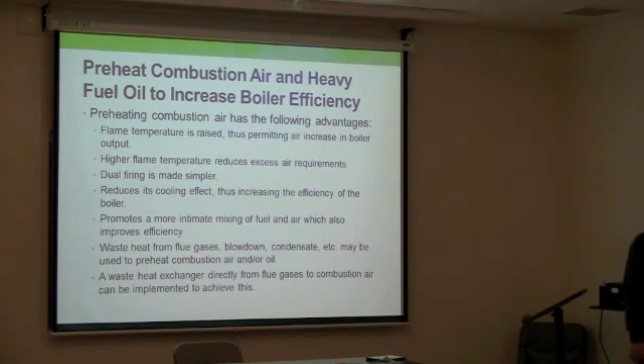A lot of times the combustion gas, the flue gas that is leaving the stack and is supposed to go to the air, right? You can use it for different purposes. It's very hot air. Why do you want to let it go? Of course that hot air is full of CO2 and NOx. You cannot use it as air conditioning, for example, and put it inside the room, right? But you can use it in an air-to-air heat exchanger, heat up clean air, and send it in the room. You can use that hot air to preheat the water that is coming to the boiler itself, right?